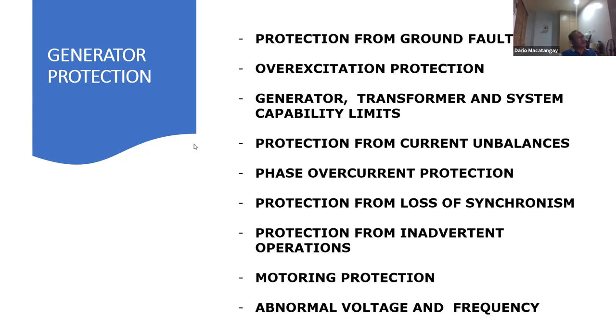Phase overcurrent protection is one thing that's different in generator protection, because the generator is different from the system when it incurs a fault, because the impedance of the generator is changing immediately after the fault. So at T0 plus, after a fault, the reactance of the generator is very small. It's the subtransient reactance. If it is very small, like in the 20% range, 0.2 per unit, that implies a very high current at the start. It's AC.